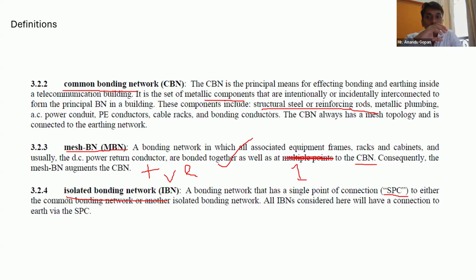Basically, what happens is all your telecommunication equipment will be bonded together. All your protective elements and your metal cables, that is your AC power conduit, PE conductor, cable racks, bonding conductors, all of these will be connected together. So between the two systems, your CBN and the isolated bonding network, you will have only one single point connection. So that will be an isolated bonding network. In an isolated bonding network, the only major requirement when you interconnect is that it must be a single point connection between CBN and IBN.